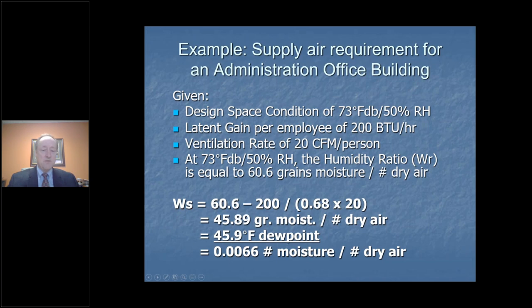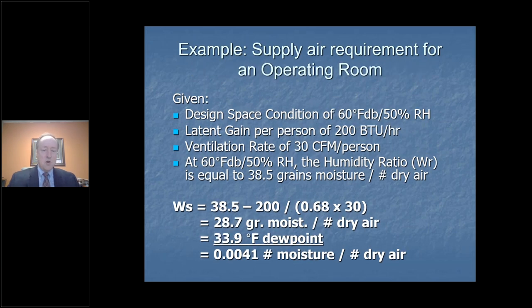and we can find these types of numbers in the ASHRAE Fundamentals Handbook, if I'm going to have a latent gain per person of about 200 BTUs per hour, and let's say I've gone through my ASHRAE Standard 62.1 and I've determined I need an equivalent of 20 cubic feet per minute per person, then I can find on my psychrometric chart these numbers and I calculate it, and it tells me that I need to be delivering that air at 45.9 dew point, or almost 46 grains of moisture per pound of dry air, in order to maintain the space requirements that I had sought out to do. We change that, we've got an operating room now, the calculations are the same. We start off at a different point on the chart and find out we need to be delivering air at 28.7 grains of moisture per pound of dry air, or 33.9 dew point.